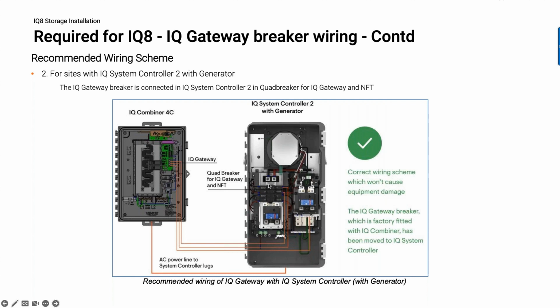Okay, all right, so the important thing to understand is that you must do this. You must, if you're installing IQ8s into a system controller 2, you must relocate the power from the gateway into the system controller. Do not do it any other way, okay? If you're installing IQ7s, different story. IQ7s, you can go ahead and just power it off here. But IQ8s, you have to then power it from the system bus.